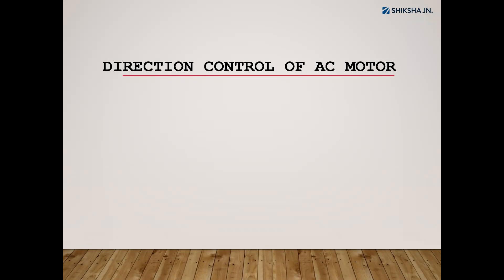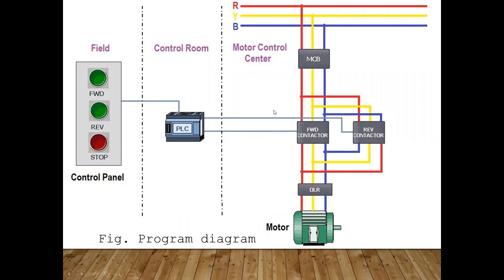We want to control the direction of an AC motor — changing from forward to reverse and reverse to forward. For that, the conventional method requires two different contactors: a forward contactor and a reverse contactor. As shown in the diagram on the right-hand side, to change the direction of any AC motor we have to reverse two of the three supply phases — R, Y, B. Any two supplies reversed will automatically change the direction.